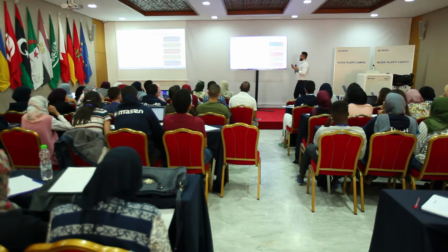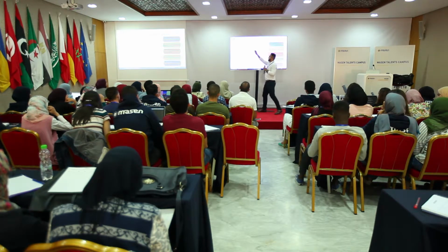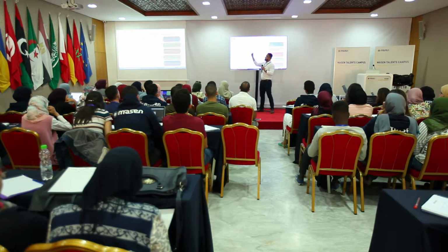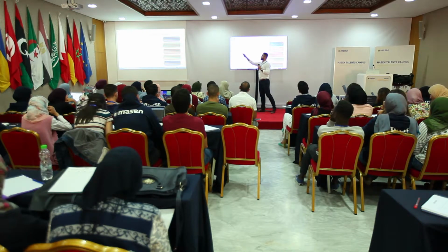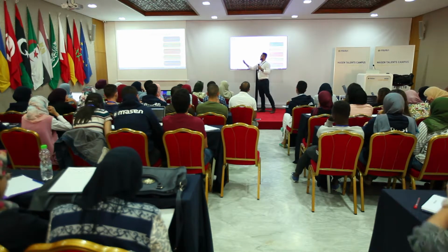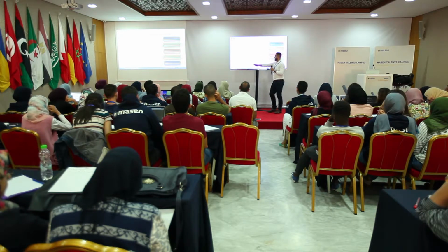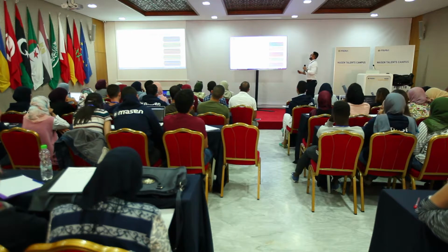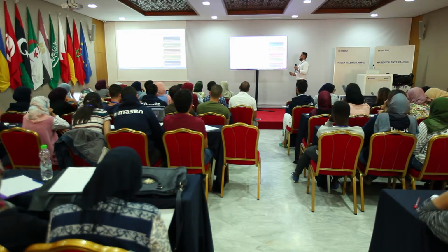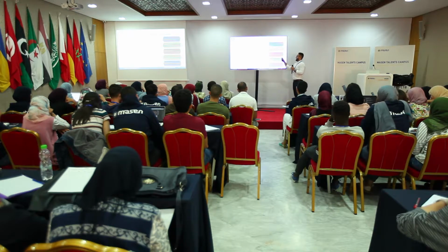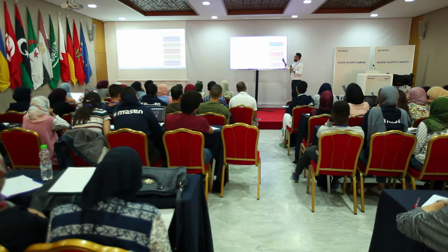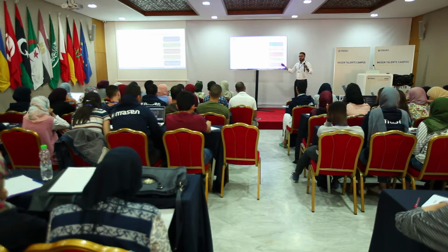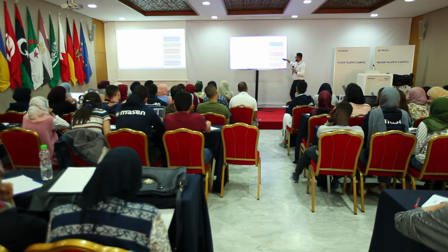The CSP is needed the most at these particular peaks you see here in a competitive market like Spain, and when it's actually able to compete with other resources, because CSP is more costly than these, for instance, but still gets recruited. You see how well CSP complements PV, because CSP can store during the whole day. At this time of day, on this Thursday, it's just storing energy. You see almost no production from CSP, very little. And then in the night, you see the peak of CSP. So that's the reasoning behind how much storage we need.